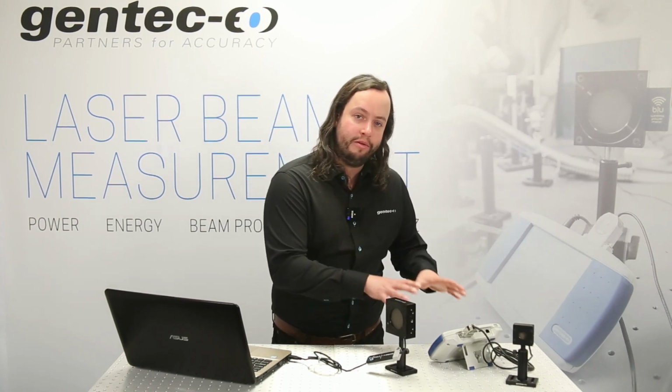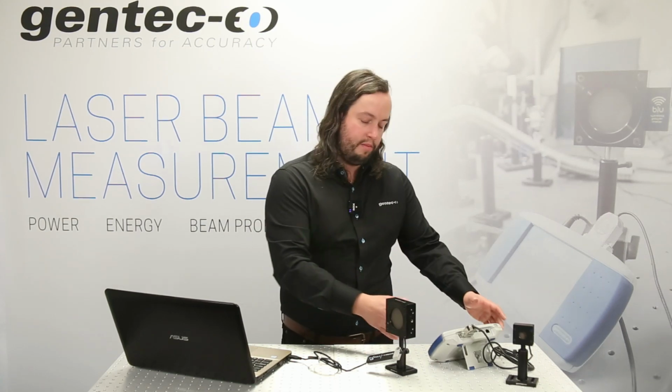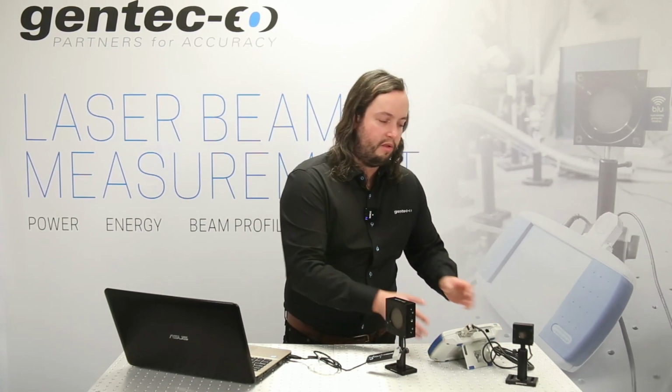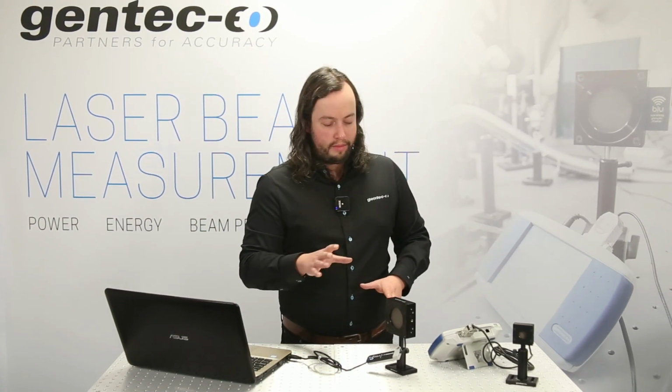Now we can try some more interesting commands. So to know which commands are available on your device, you have to refer to the manual of the meter you're using. So just to be clear, the meter is the part that processes the signal. So here, for example, I have a Maestro and a UP detector. So the serial commands that I can use for this combo are going to be in the manual of the Maestro, or the Miro if you have the Miro. For my USB detector right here, I'm going to go in the Integra manual.